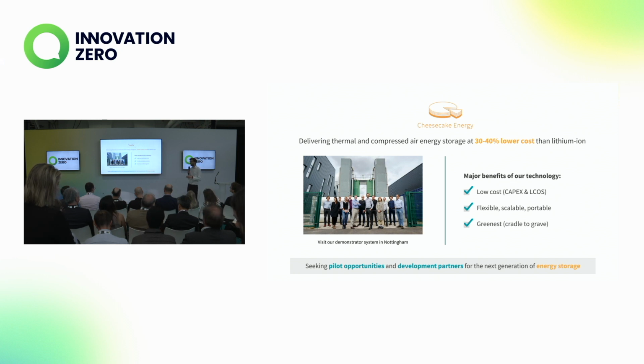Yeah, so the unit is 150 kilowatts so we can ramp up to that speed relatively quickly when we're spinning. If we are stationary, if we'd been shut down for a while, then we will need a bit of time to spool up, in the same way a diesel generator would. There's a lot of similarities between us and a diesel generator, except the emissions. We're not a fast frequency response solution - other technologies do that really well, we're happy to leave them to it. This is about moving power en masse from certain times of the day to other times of the day. We can provide inertia because it's synchronous electrical machines, which is often valuable. But we're not a sports car - we're more like a truck in terms of the way we respond.